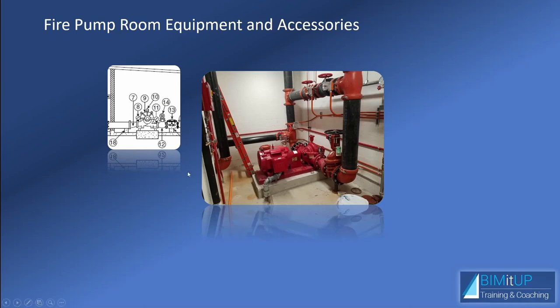Like right here, you see a typical fire pump. Here are some of the components. You can see the suction would come from the left here in the image. So you have typically an eccentric reducer here to avoid air pockets that you would see on the right hand side. You have a main isolation valve. It's typically an OS and Y valve. Then you have your pump itself, in which you can see the suction and the discharge pressure gauges. You see also an air release at the top of the casing. And then at the discharge, you have a check valve.